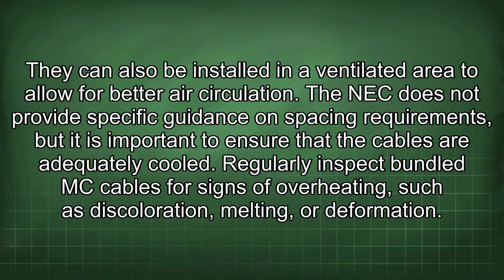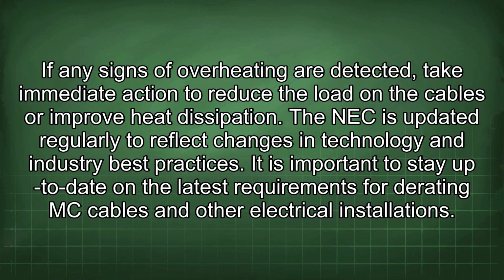Regularly inspect bundled MC cables for signs of overheating, such as discoloration, melting, or deformation. If any signs of overheating are detected, take immediate action to reduce the load on the cables or improve heat dissipation. The NEC is updated regularly to reflect changes in technology and industry best practices. It is important to stay up to date on the latest requirements for derating MC cables and other electrical installations.